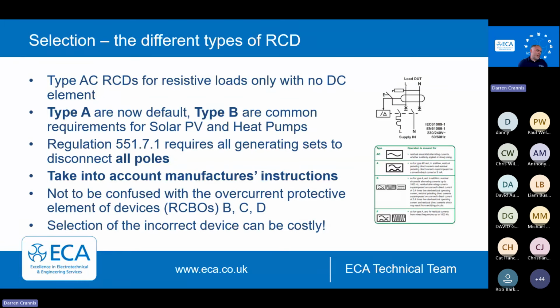You might start seeing type B being specified, maybe for solar PV, if that's how you choose to install your cables in walls, and possibly things like heat pumps. When selecting your RCD, it's important that if you've got generating sets, so solar, battery storage, they are all generating sets. We do need to disconnect all the poles, and that also includes the neutral.